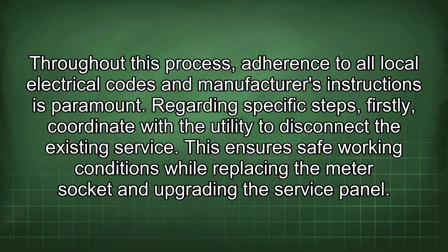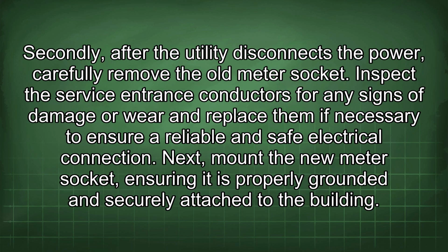Regarding specific steps, firstly, coordinate with the utility to disconnect the existing service. This ensures safe working conditions while replacing the meter socket and upgrading the service panel. Secondly, after the utility disconnects the power, carefully remove the old meter socket. Inspect the service entrance conductors for any signs of damage or wear and replace them if necessary to ensure a reliable and safe electrical connection.